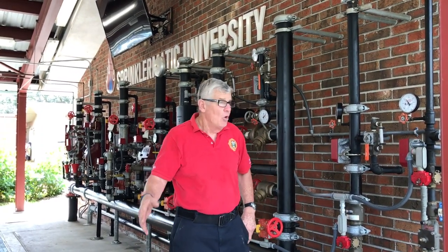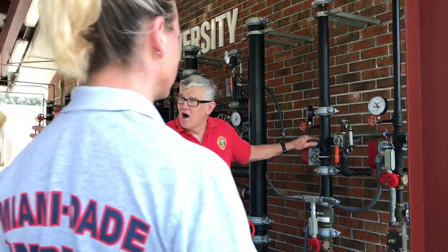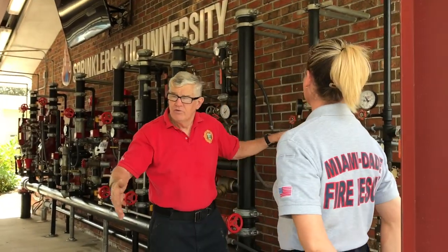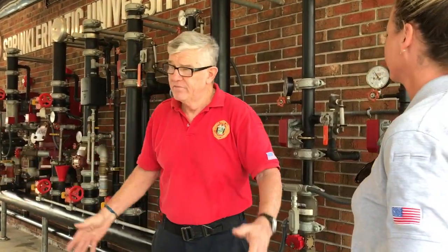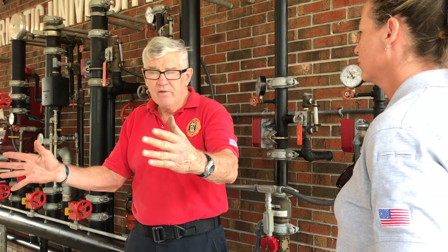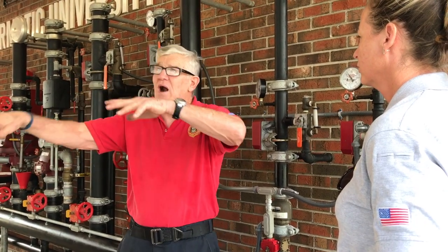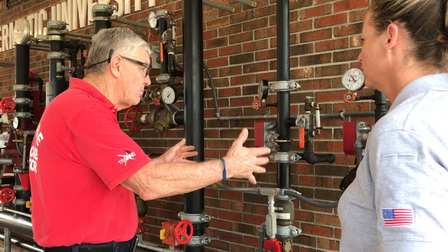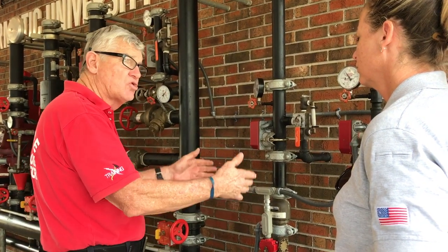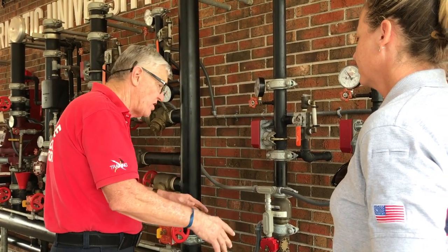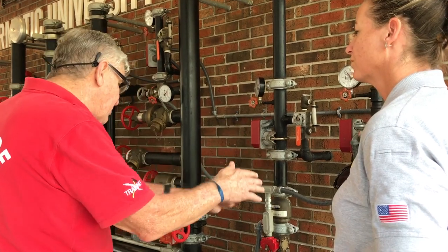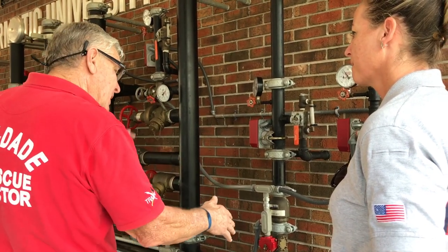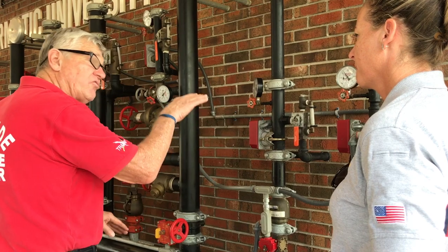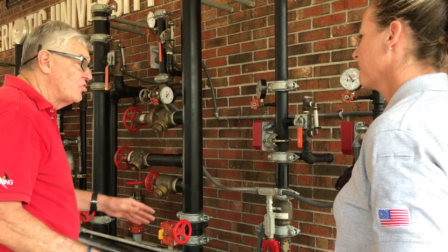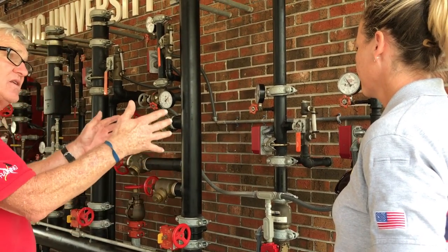Now, where do we see this, just for our Miami-Dade guys? They're all over our county. Semi-enclosed stairway, where you have four apartments at a landing. You'll find a cabinet outside the building, and the maximum stories you would have with this would be three stories. You usually are looking at a cabinet and there's three pipes coming out, and it'll be for first floor, second floor, third floor. So you want to try to find that cabinet on the side of the building.